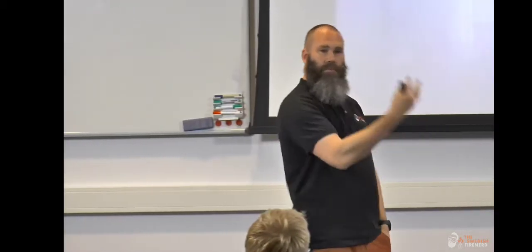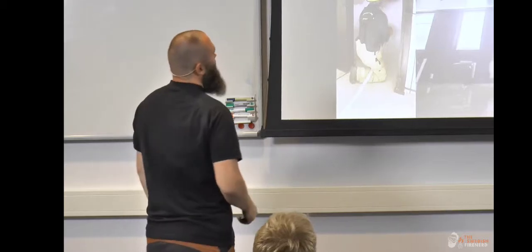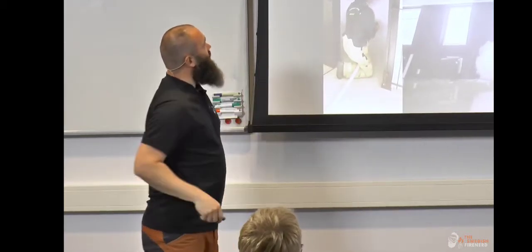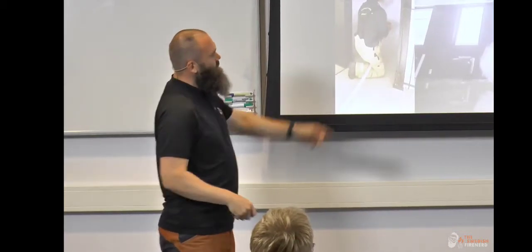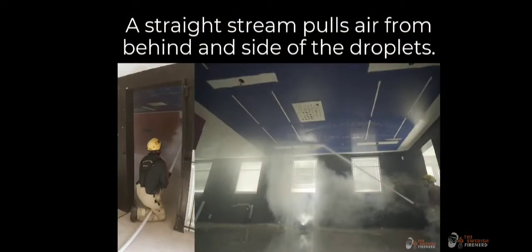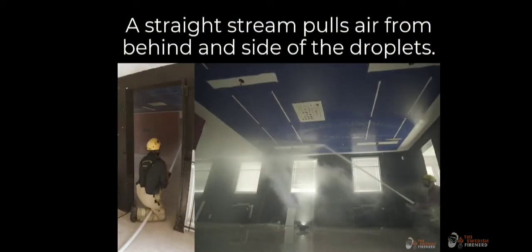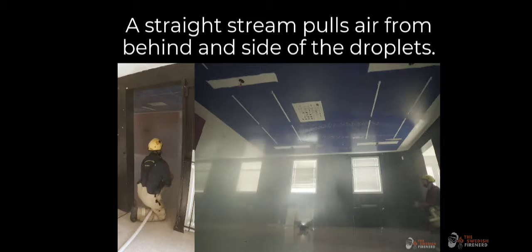But anyway, the physics of it is that you will entrain things up here and pull it down, or you will entrain things down here and pull it up. It's just physics. A straight stream pulls air from behind and the side of the droplets. It's just that the straight stream creates the droplets up here instead of here, it goes up into the stream. So wherever the straight stream breaks up into droplets, that's where you have the entrainment.